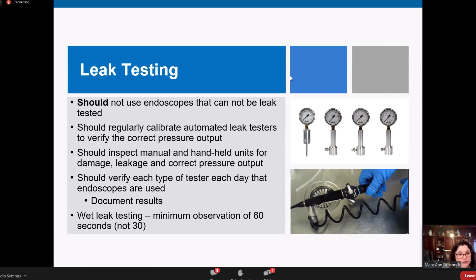So we do now say that you should inspect your leak test units for damage and leakage and the correct pressure output. What that means is, as far as the standard goes, we now recommend daily, every day that it's used, that you verify the output pressure from that leak tester and document that. That is something we're asking to be documented. I've seen many, many instances where I go in and test a leak tester, and sometimes they're making a sound and they're not outputting any pressure at all because an O-ring went somewhere and all that air is escaping, or something else is damaged. So there are various different testers on the market. You can work with facilities or your biomed to figure out how you're going to do it, but test your leak testers and document it and make sure that they're regularly calibrated.